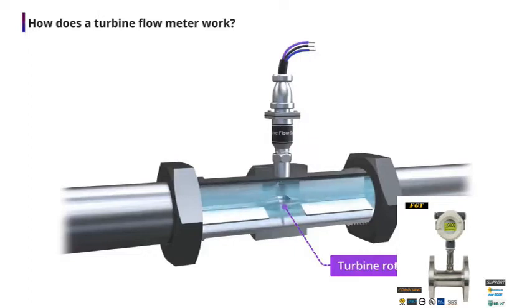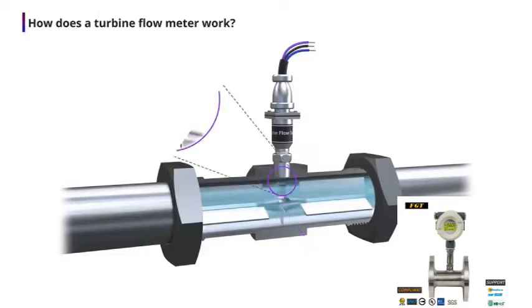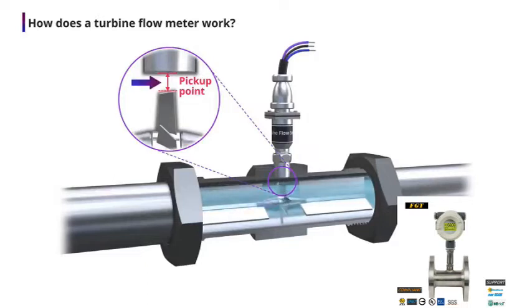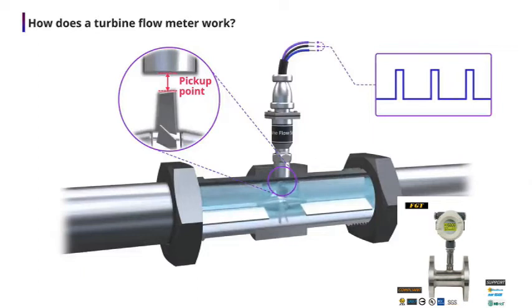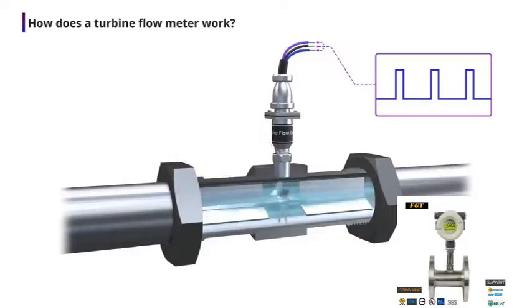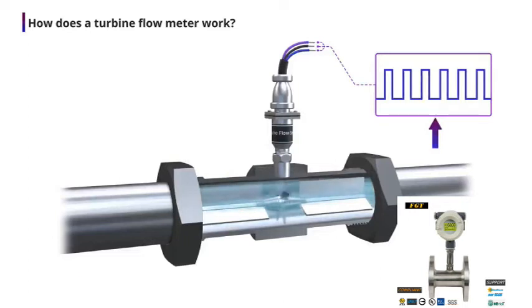The rotor blades are usually made of stainless steel. As the rotor spins, the passage of each rotor blade past a pickup point will generate an electrical pulse. The electrical pulses are created in different ways, depending upon the rotor blades themselves and the pickup unit characteristics. In most turbine flow meters, magnets are fitted to the blades, and a magnetic pickup sensor is used to create the pulses. The higher the rate of flow, the faster the rotor turns, and the greater the number of pulses.